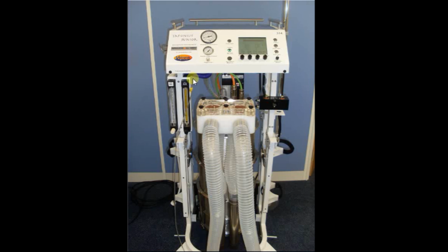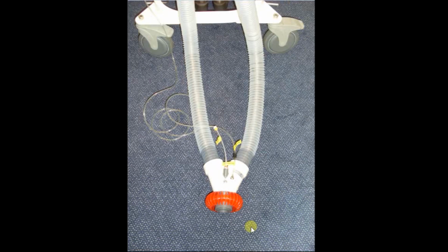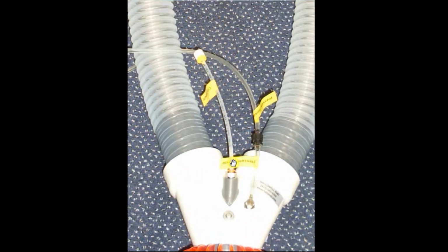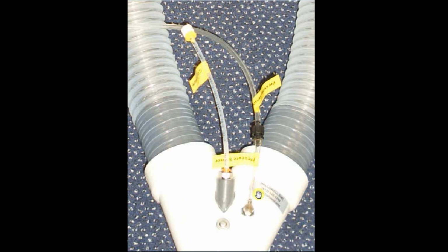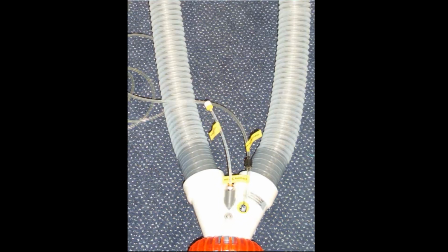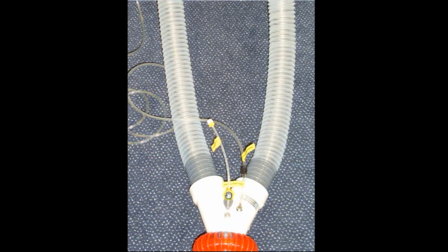It connects to a little luer connector here, and as we see on this slide, it comes down and connects to a little luer connector here, which takes it to a little swivel head connector which senses or measures pressure in the Y piece. And this is crucial to the way Tafonius, not only in Junior, but all machines work. The way it works is that whenever an increased pressure or fall in pressure is sensed in this Y piece by as little as 0.25 centimeters, the machine will then, in servo mode, move to negate that pressure change.